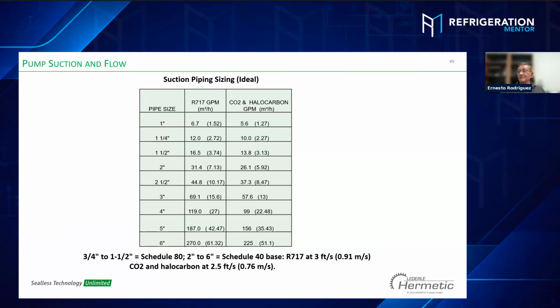I said, this is the reason you need to replace mechanical seals every 3 months or 6 months, because of the problem with the undersized pipe. After they replaced the size with 4 inches, they were able to correct the problem.